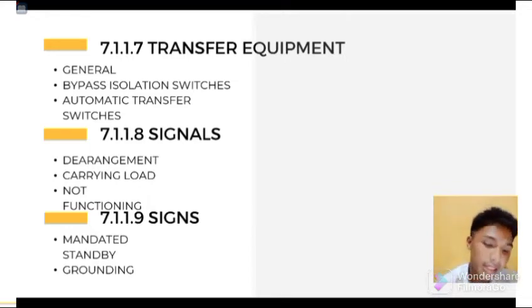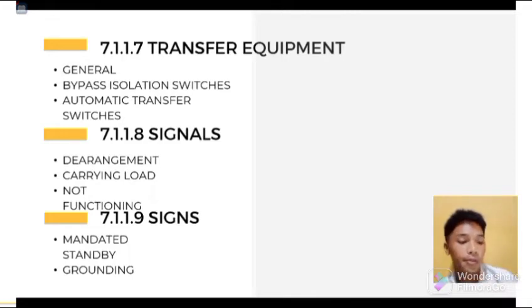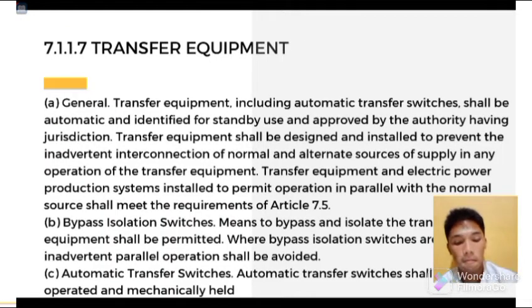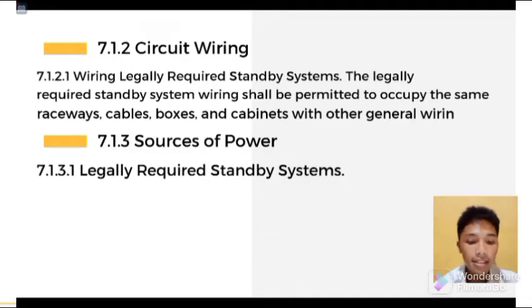And there is only one exception for this. That is, a sign shall not be required for individual unit equipment as specified in 7.1.3.1, letter G. Letter B. Grounding. There shall be a sign at the grounding location that shall identify all legally required standby power and normal sources connected at the location. Circuit wiring. Wiring of legally required standby systems. The legally required standby system wiring shall be permitted to occupy the same raceways, cables, boxes, and cabinets with other general wiring.